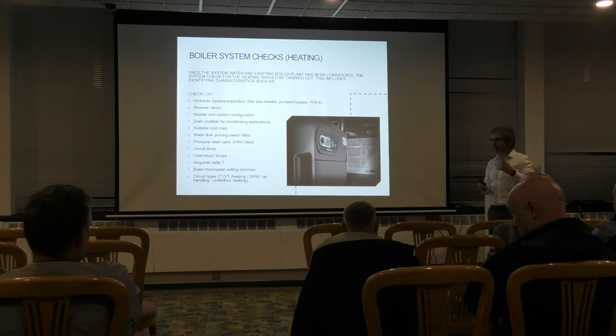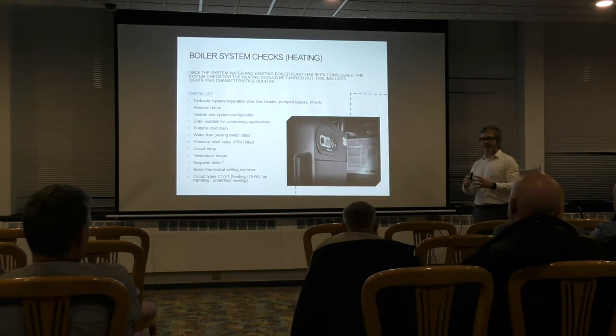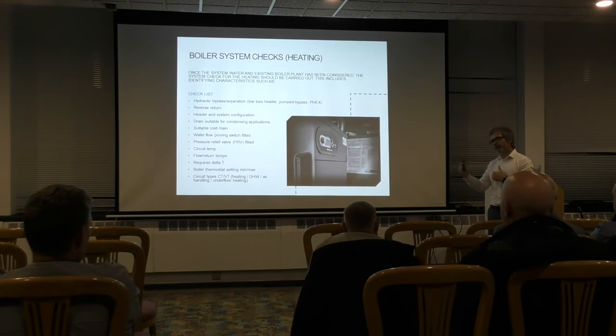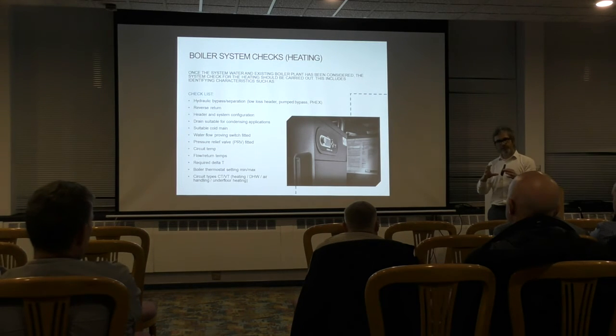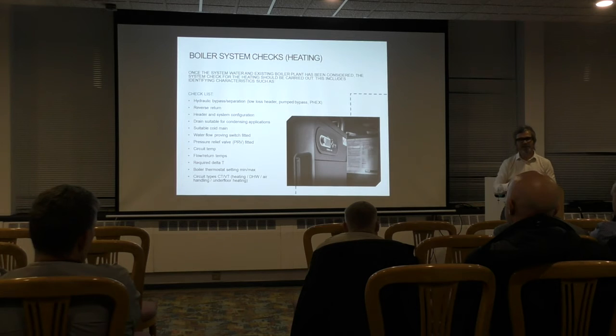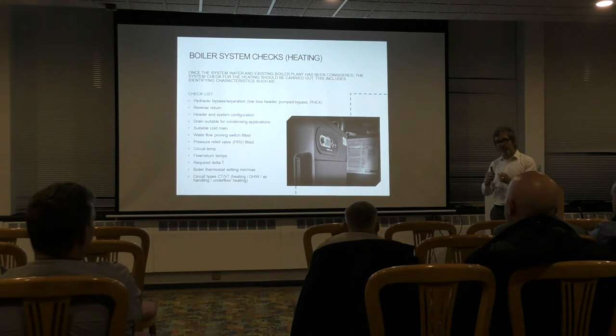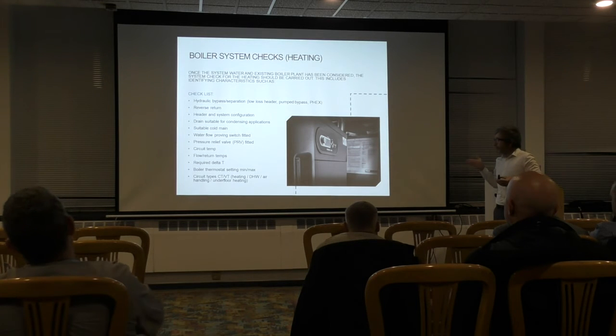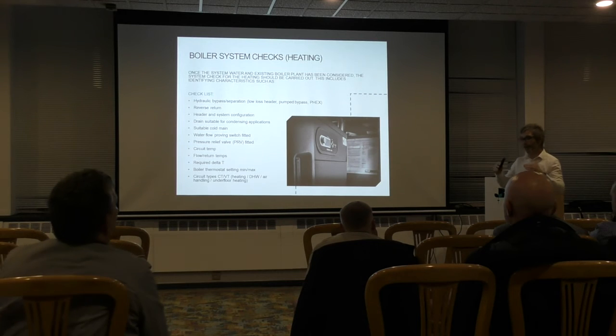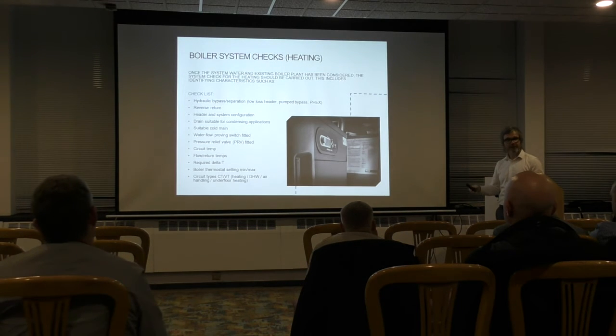But the problem you have is that when we're looking at older boilers, waterways were a lot larger. So when we're looking at narrower delta T's, we're looking at a higher flow rate. On a larger waterway, we're putting that water through at a higher flow rate. It's not a problem, we can use a smaller pump, it gets through there. There's not a great deal of pressure drop through the boiler. Put a condensing boiler in, for modern boilers to be as efficient as they are, we've had to reduce the size of the waterways. So now we're trying to put the same volume of water at the same flow rate through a smaller hole, essentially. So what that means is we now need to use a bigger pump because we've got a higher pressure drop. And is that really the most efficient way of doing it?